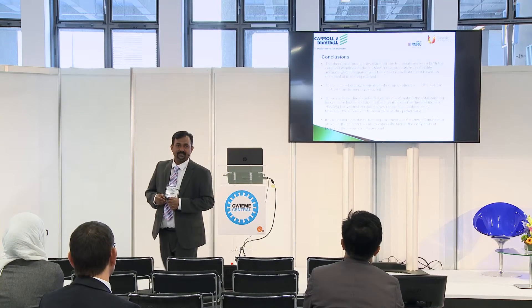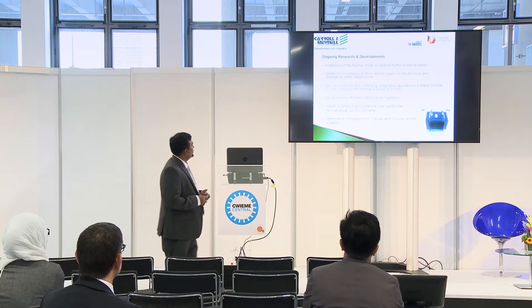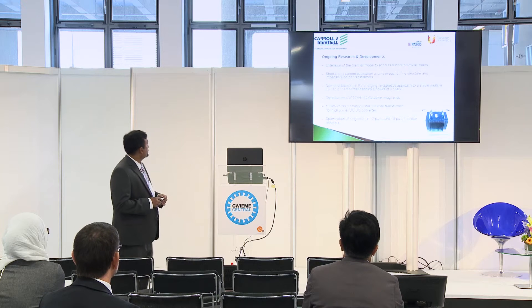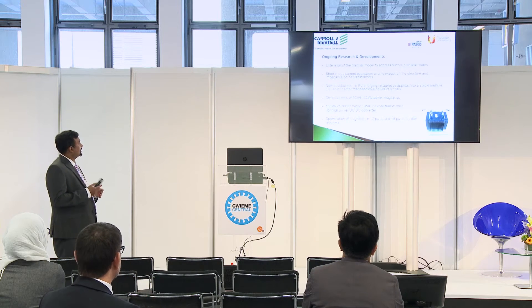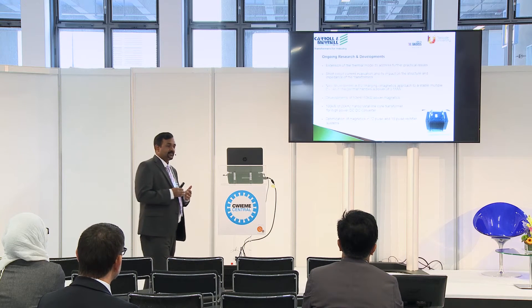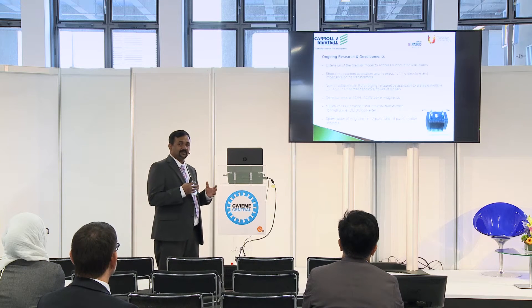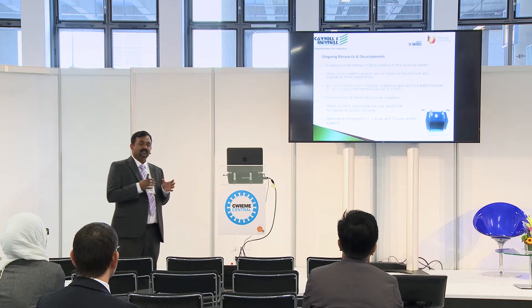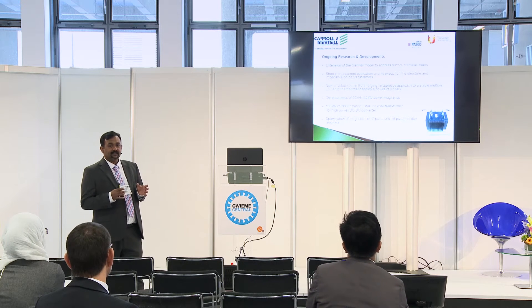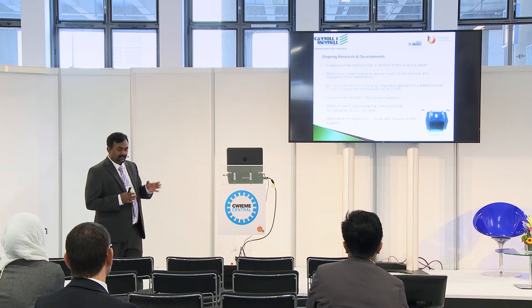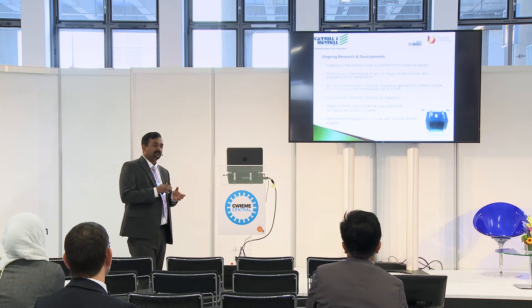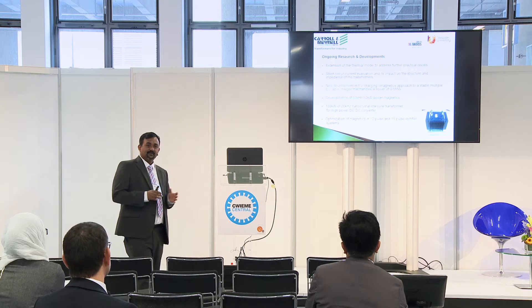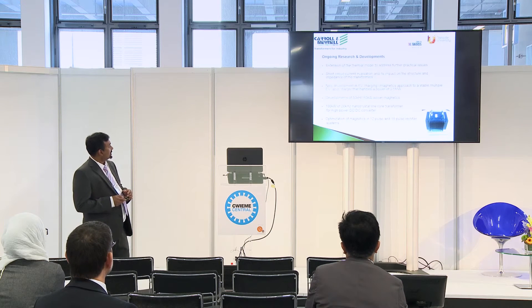As further development, we are doing more work in this direction to be capable of constructing unusual products with demanding specifications like single-phase megavolt-ampere range. Apart from this, we are carrying out a number of R&D activities at the company. One is the extension of these thermal studies. Another interesting activity is the evaluation of short circuit conditions on a dry type transformer — specifically evaluating the effect of short circuit forces on the transformer structure and how they affect the physical shape, and thereby the inductance and impedance. It involves a transformer with several taps and about 600 kVA size.